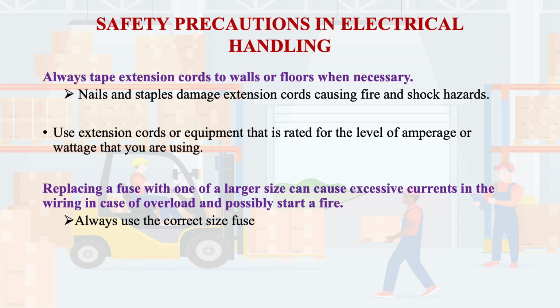A remedial measure you can take is to always use the correct size of fuse. This is normally seen with contractors in the industry. Whenever they are using some electrical equipment, if the fuse is frequently failing, then they will use a higher rating of fuse, or a higher size of wire, so that it does not fail again. Consequently, this overloading results in a possible fire.